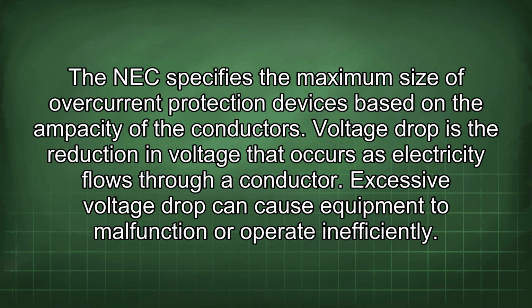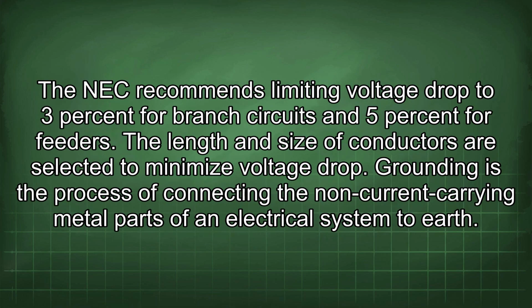Voltage drop is the reduction in voltage that occurs as electricity flows through a conductor. Excessive voltage drop can cause equipment to malfunction or operate inefficiently. The NEC recommends limiting voltage drop to 3% for branch circuits and 5% for feeders. The length and size of conductors are selected to minimize voltage drop.